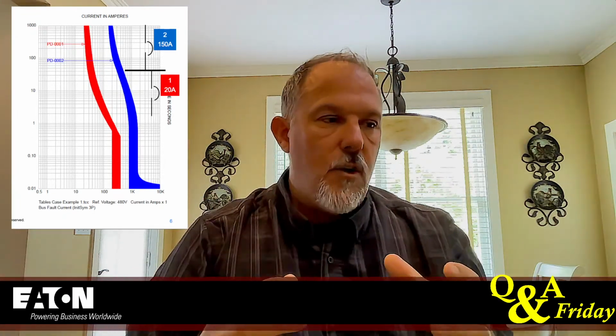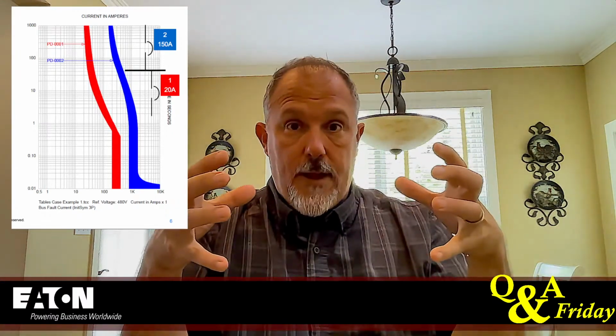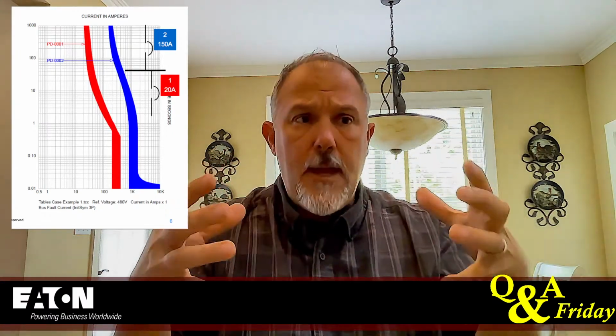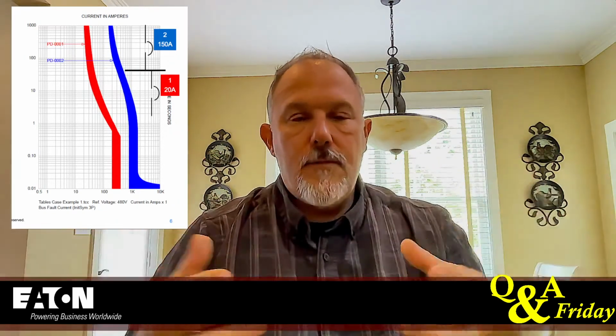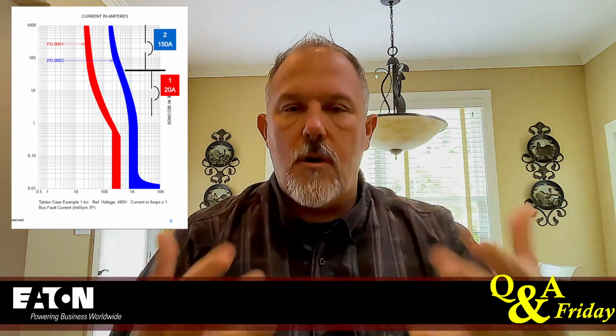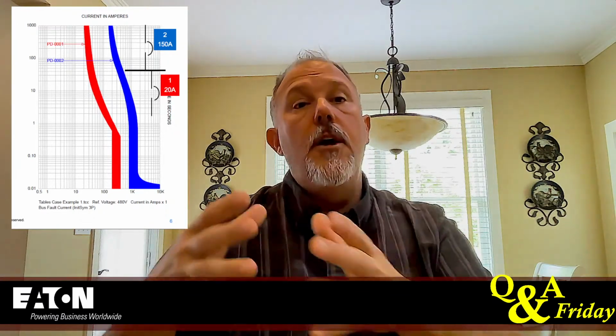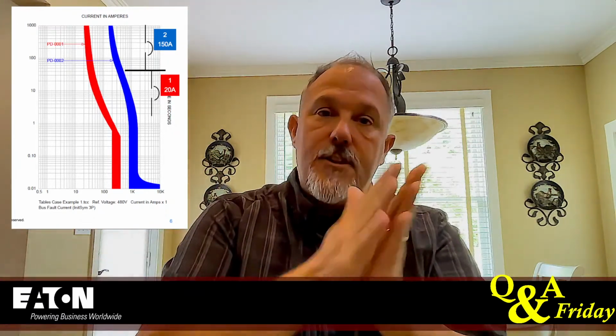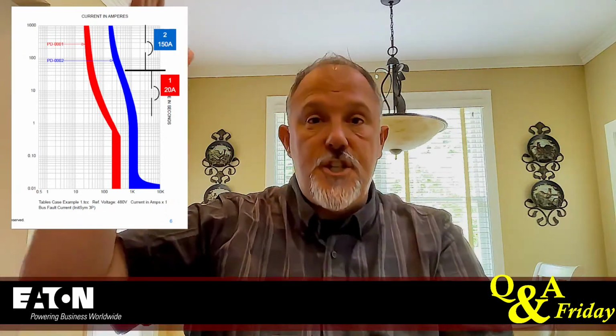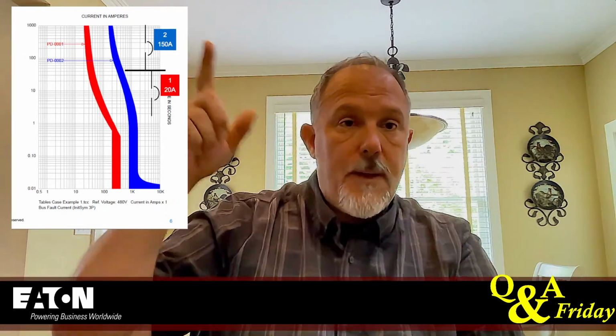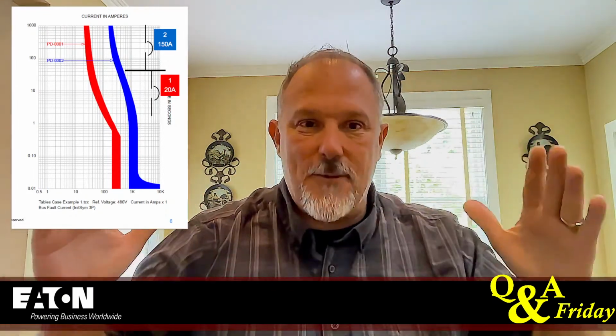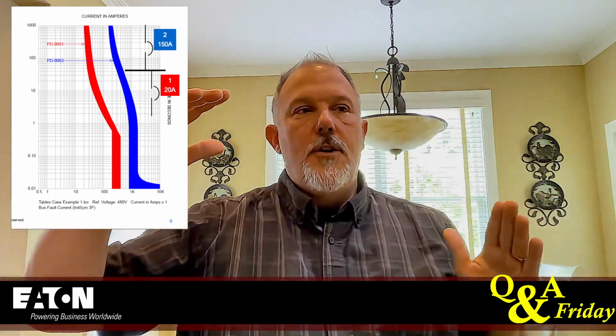So what does the frame do? When I go from a smaller frame to a larger frame, I've got more beef in there, more metal, stronger springs to hold those contacts closed for those higher fault currents. And then I can adjust my long time pickup. What I should do is, I can't do that, I don't have my green screen. I'm in my kitchen right now. So I can move my long time pickup down.